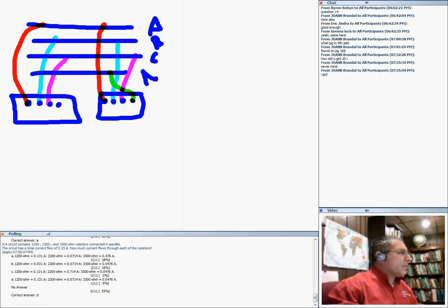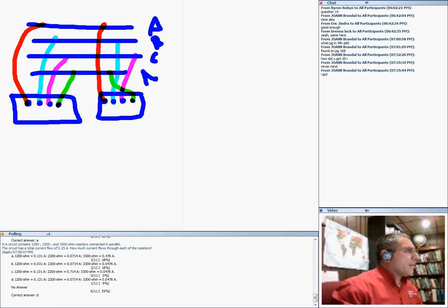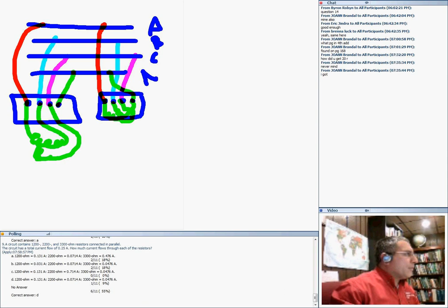That's the structure. And for what's inside these generators, guys, if anybody's wondering, right inside them, this is the wye, so the winding here goes here, and the other phase goes here, and the neutral to the center. So right inside it's going to look like this, and phase B going this way, phase C going this way, and all the way my neutral going right here to the center. So that's putting the conductors together, paralleling generators.